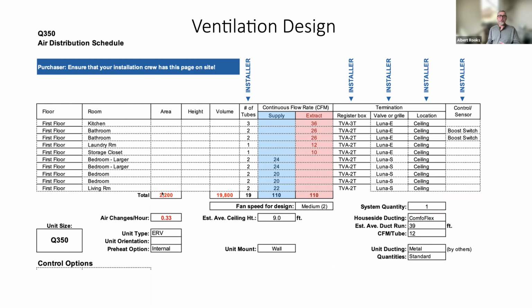So we've established, really based on the volume of the room and the occupancy, what our supply flow needs are. So now we'll take a look at the exhaust rates. In a kitchen, different things could be happening, right? A lot of kitchens have range hoods that are a 300 CFM fan and you turn it on for a while you're cooking, and it depressurizes the house and pulls the burning pizza smoke that I make out and sends it outside of the building. But in a balanced ventilation system, we can also add a solid 36 CFM exhaust flow into the kitchen.